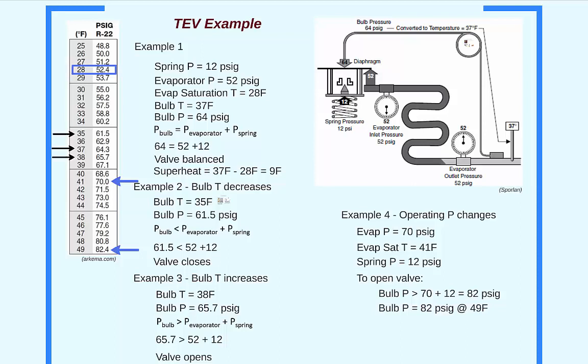The superheat at this point is the difference between 49 degrees and 41 degrees. Even at this new operating pressure, the superheat remained relatively constant, and that will be the case across the typical operating range of evaporator pressures these systems operate at. You can try similar examples yourself using different operating pressures. You'll find that the spring pressure set in the thermostatic expansion valve creates a near constant superheat temperature that is controlled independent of the load or operating pressure in the evaporator.